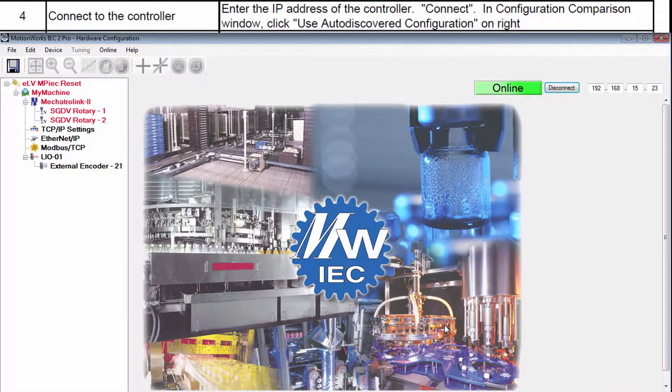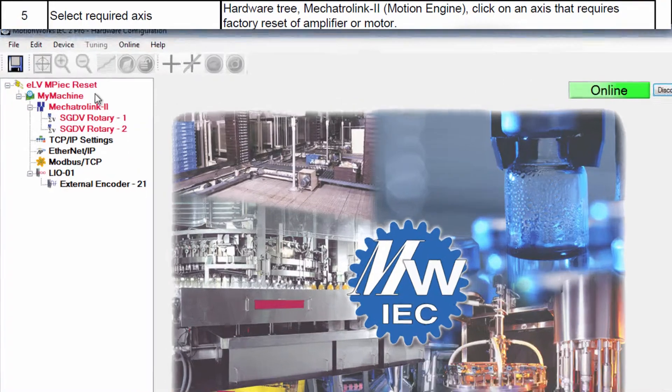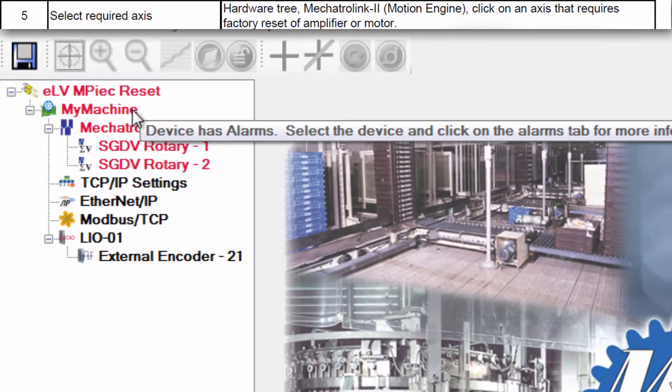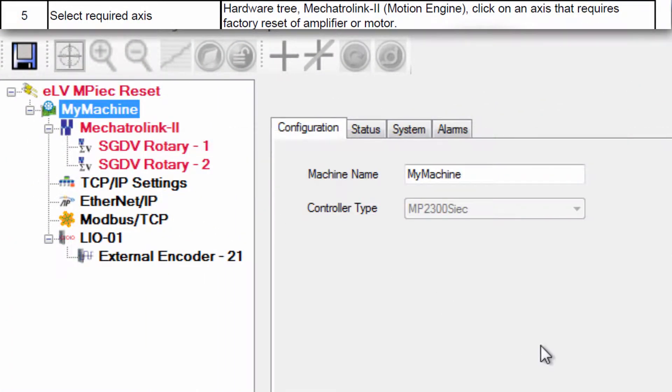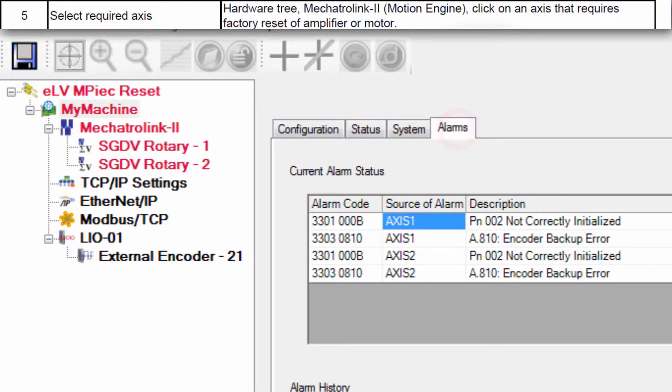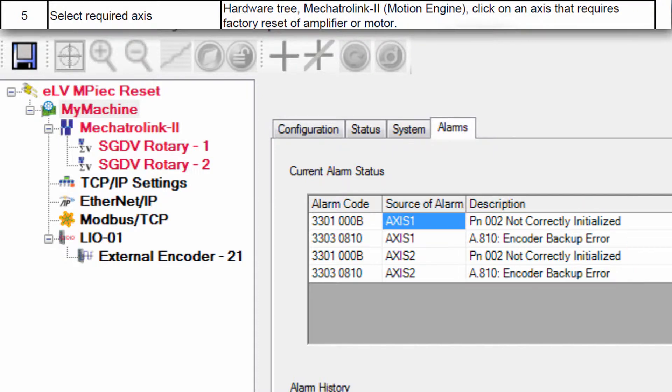Now we're online and you can see a lot of red in the hardware tree indicating alarms. On my machine in the alarms tab each axis is complaining about PN002 not correctly initialized and Encoder Backup Error. This is normal and expected the first time you connect a new servo to the controller.